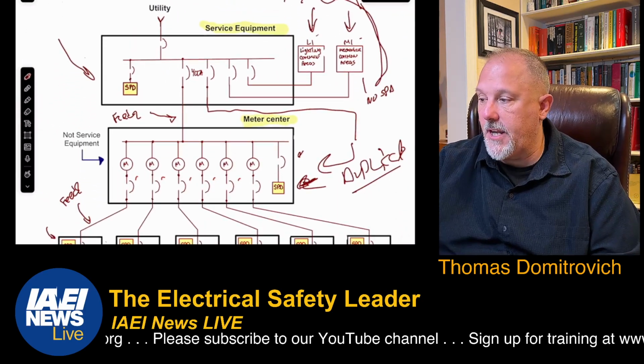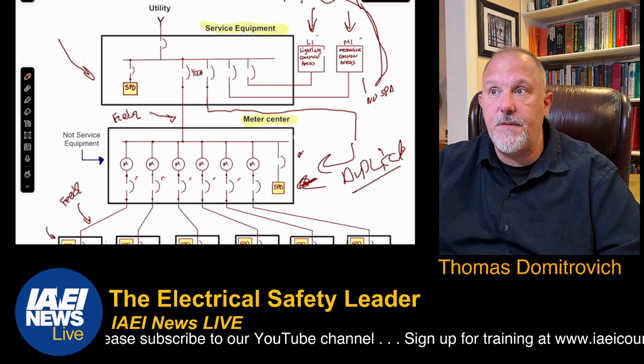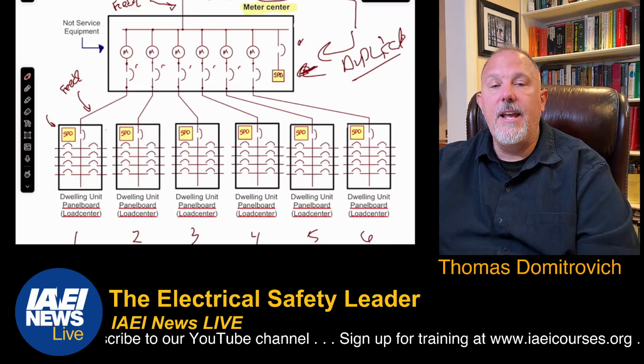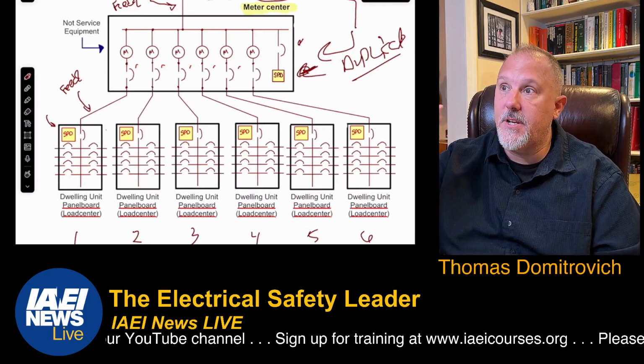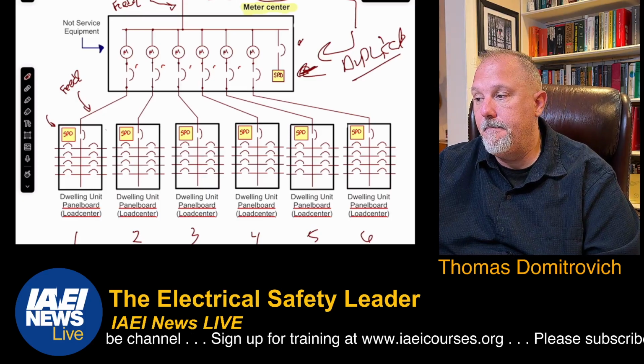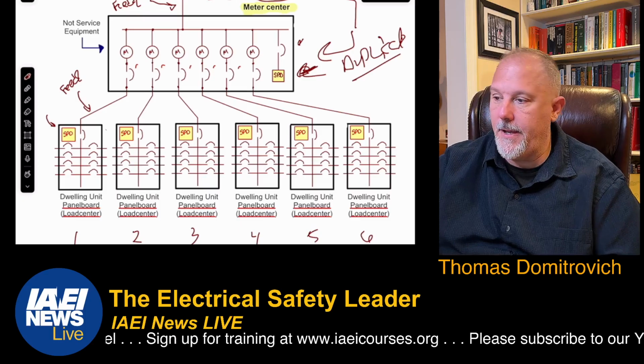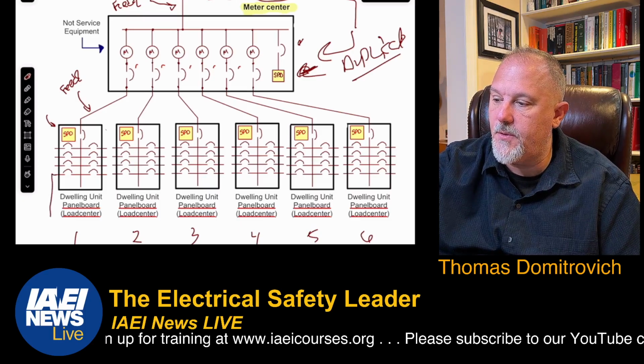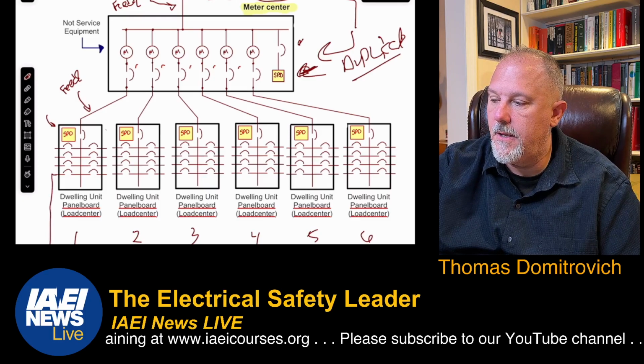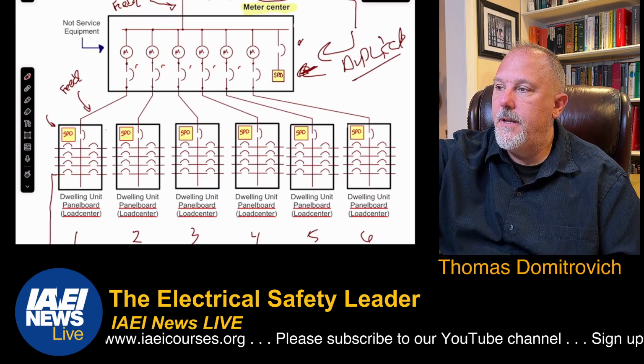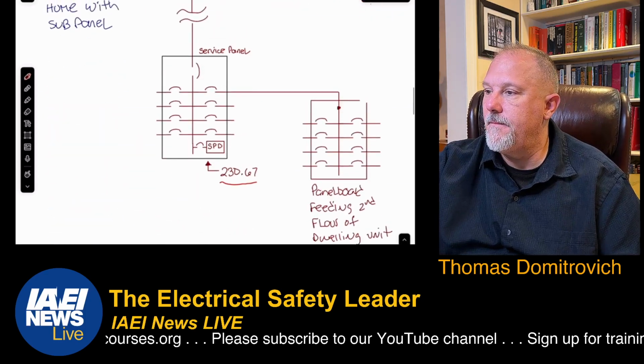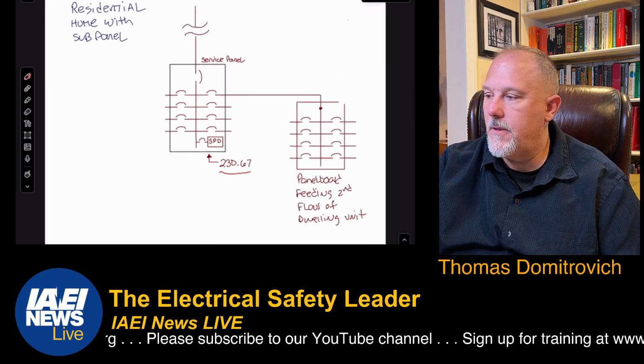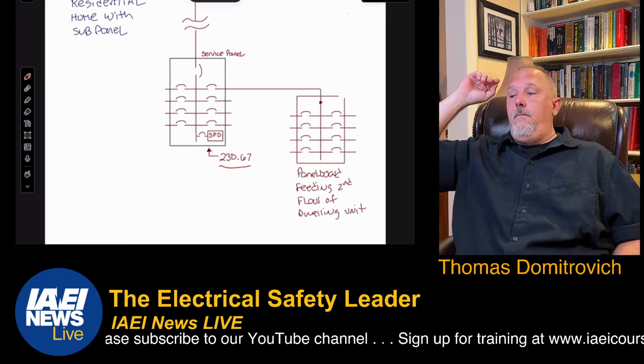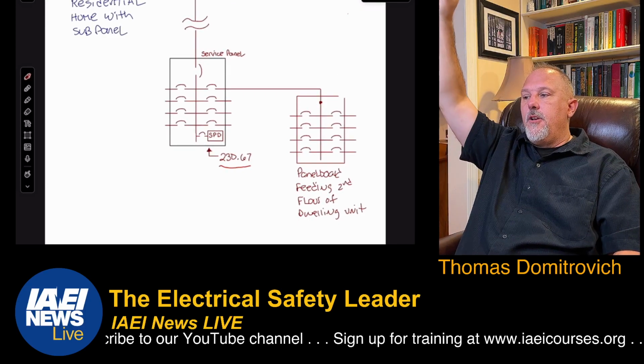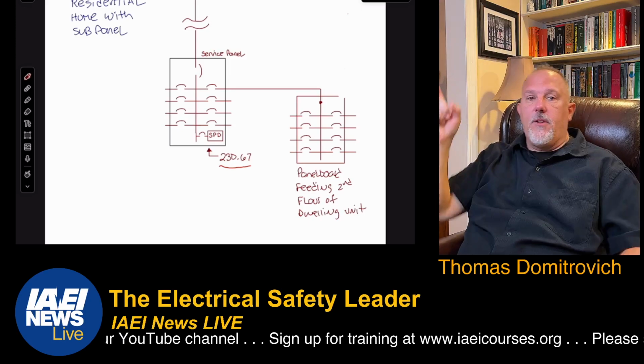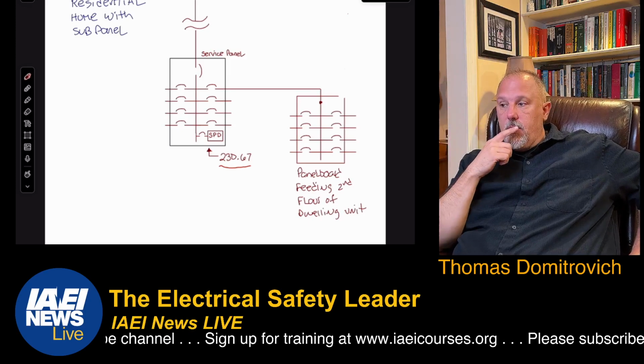And then all of the meter centers have to have a surge protective device because of 215.18, and each of the dwelling units have to have a surge protective device because of 215.18. Now, the gray area was if in the dwelling unit I fed another panel. So it's very similar to this house here. So you have a residential panel, and the panel board in my dwelling unit here goes upstairs to a panel board upstairs that feeds the circuits on the second floor.